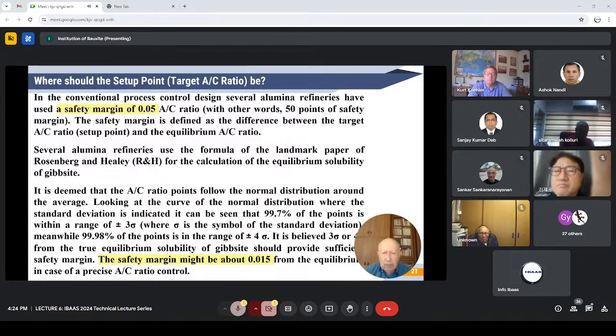An interesting question: where should the setup point, in other words, the target A to C ratio, be? In the conventional process control design, several alumina refineries have used a safety margin of 0.05 A to C ratio, in other words, 50 points of safety margin. The safety margin is defined as the difference between the target A to C ratio, the setup point, and the equilibrium A to C ratio. Several alumina refineries use the formula of the landmark paper of Rosenberg and Healey for the calculation of the equilibrium solubility of gibbsite.